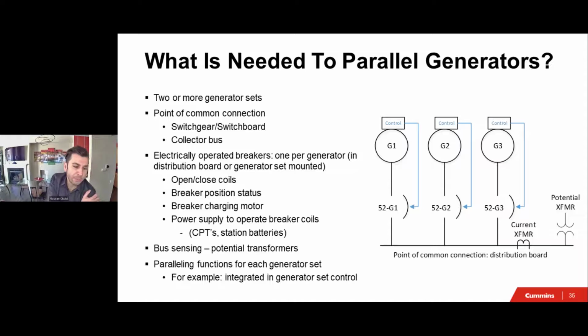We need electrically operated circuit breakers, one per generator, and we need to be able to open and close. We need to get the breaker position, so an A contact. There will be a breaker charging motor. This is something a lot of the manufacturers of switchgear and switchboards, obviously, will include in their circuit breakers. You need to have a power supply to operate the coils, some kind of a power source. Typically, that's CPTs or station batteries.